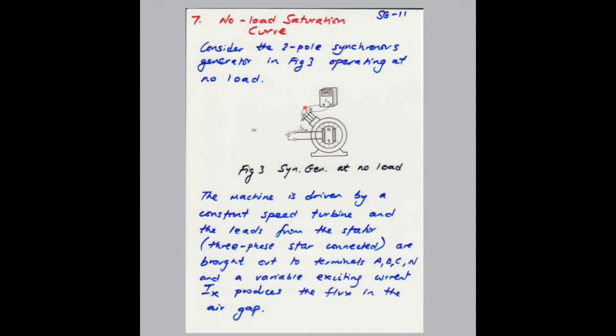And we're trying to produce what we call the no load saturation curve. So what we're doing is drive the machine at rated speed, right? And we slowly increase the excitation field current from 0 to its rated value. And obviously, as you can see, the terminals of the machine are on open circuit, so it's on no load.